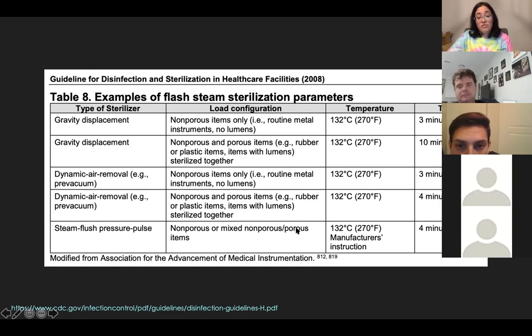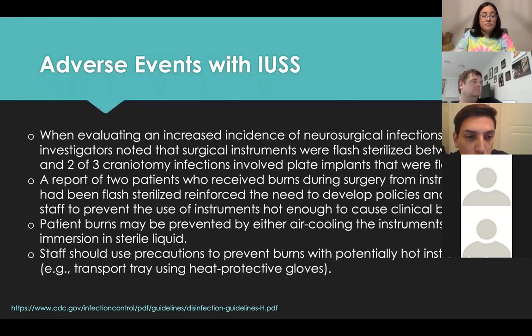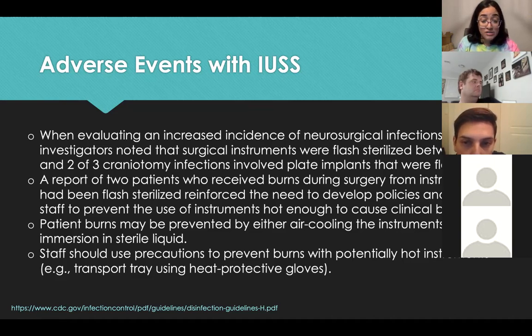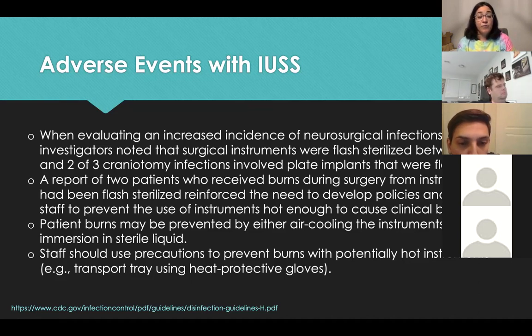Adverse events associated with IUSS include: an increased incidence of neurosurgical infections where instruments were flash sterilized between cases, including two of three craniotomy infections involving plate implants that were flash sterilized. There were also reports of two patients who received burns from instruments that had been flash sterilized, reinforcing the need for policies and staff education. Patient burns may be prevented by air cooling the instrument or immersing it in sterile liquid. Staff should use heat-protective precautions like transport trays or heat-protective gloves.